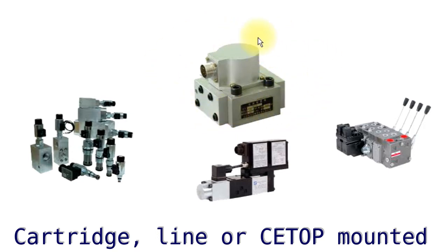This is a traditional servo valve. Performance - really, servo and proportional valves, the top end proportional now are as good, if not better. So the term servo and proportional does get a little bit confused. Traditionally this has a flapper inside controlling the spool. That was the traditional servo. This is purely electronic, so rather than a flapper controlling the feedback we've got a lot of electronics.